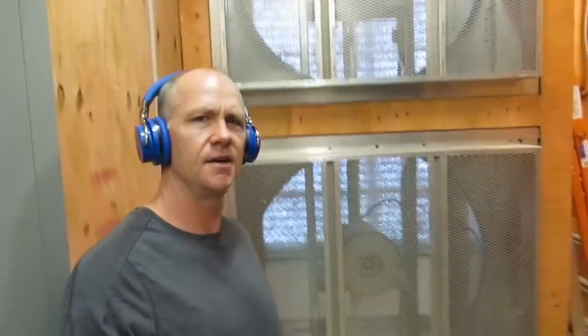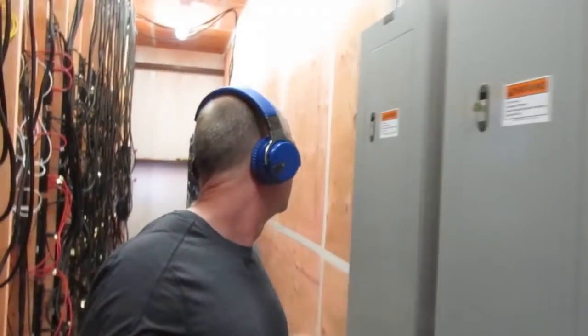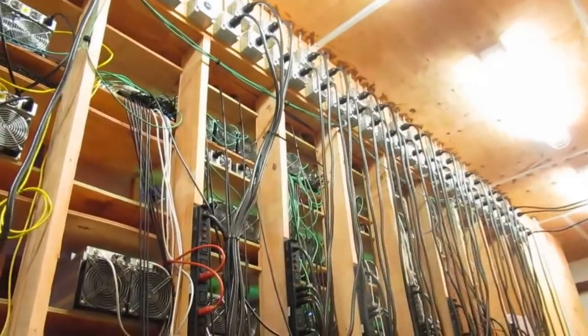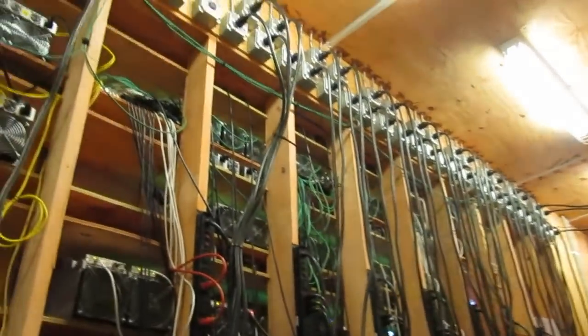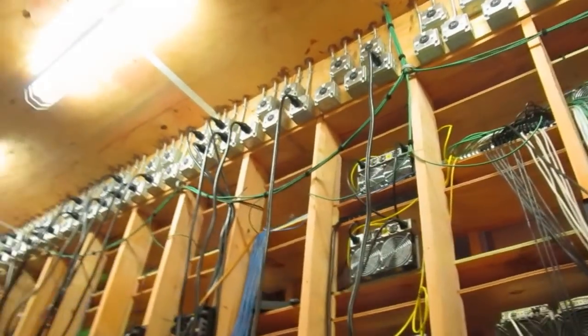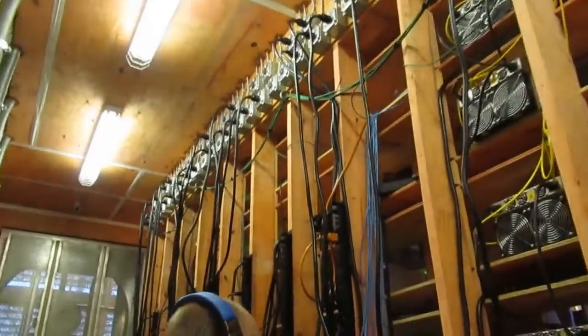So we have 2 cold aisles, and it's a little bit windy here. And from here in the cold aisle, you see that we have sub-panels, and the fans just continue to blow. So this, with both intake and exhaust fans, we have static pressure on the room. Now these panels here are the sub-panels that go to the individual 30 amp connections, and you can see that if a breaker trips, we can come here and reset it, but then we also need to go reduce the load. Up top here, we have the 30 amp receptacles. These are L630R receptacles, standard, that go to PDUs. We like the flexibility of the receptacle and PDU combination.